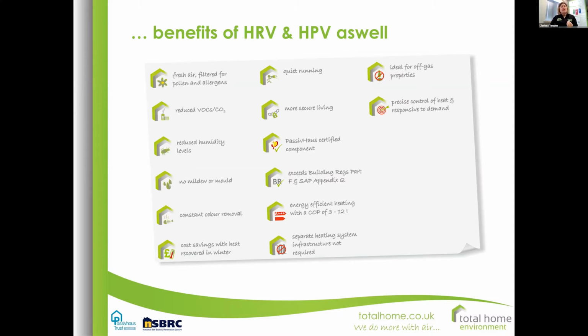Because you're using the ducting from the ventilation system, you're not going to have any other infrastructure to add. So you're not going to have any underfloor heating that has to be put into the floor. So, you know, installation times are all a bit quicker. And obviously, if you're off gas, this sort of system, along with air source heat pumps, of course, is ideal for off gas properties.